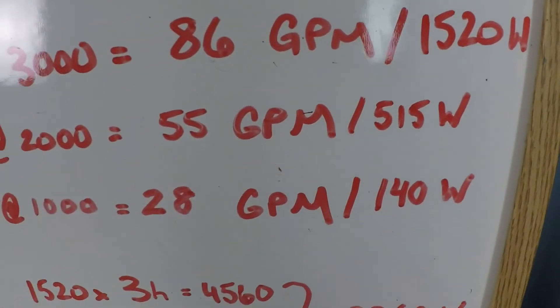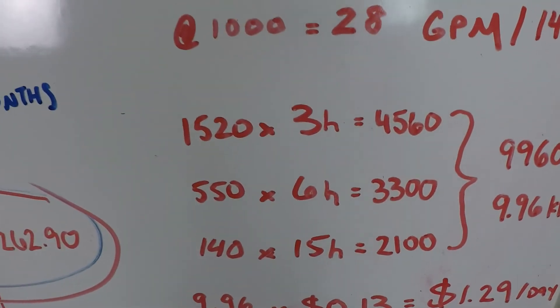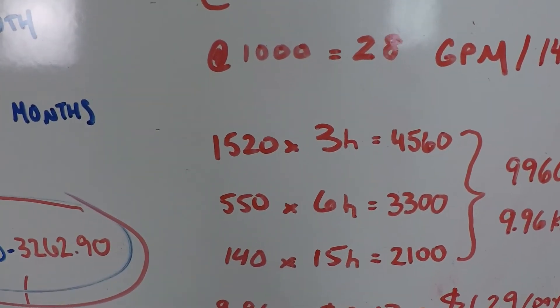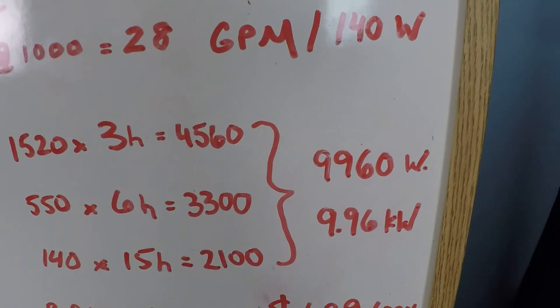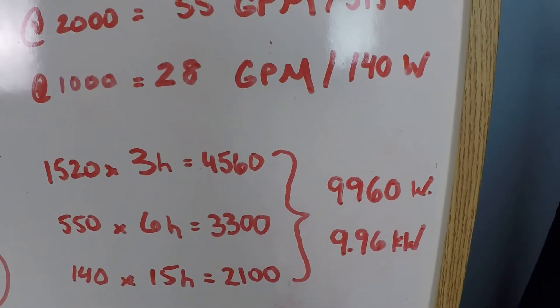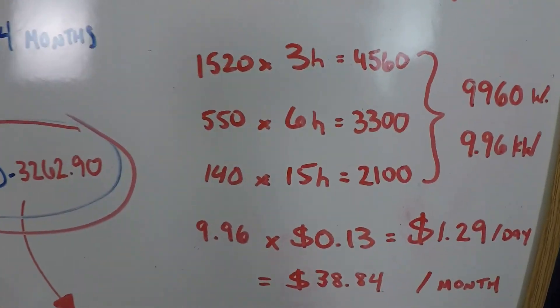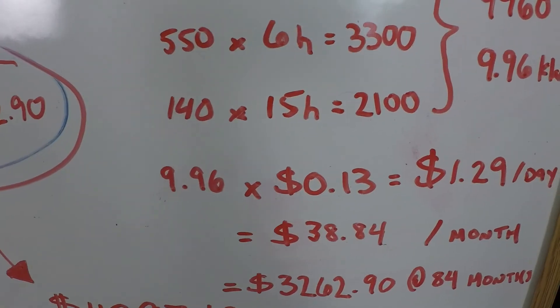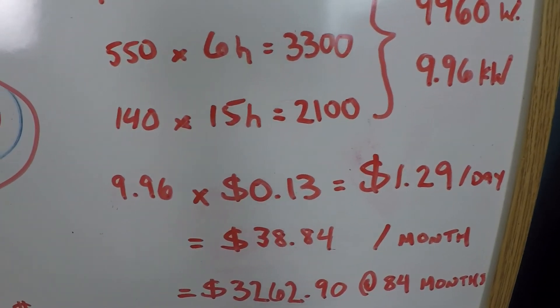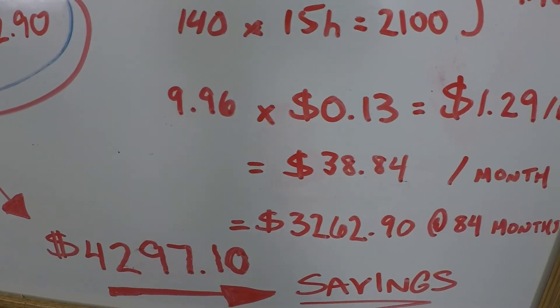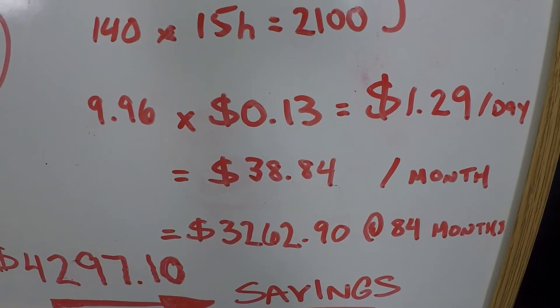So this is even a very conservative estimate at 140 watts, which is good. Because what you're going to see is that the variable speed pump costs substantially less to operate. So when we calculate out our total power consumption over a 24-hour day, we're looking at watts times hours, and we see that the total consumption for a 24-hour day is 9,960 watts, or 9.96 kilowatts. Since you pay for your power by the kilowatt hour, you would multiply 9.96 times the average of 13 cents per kilowatt hour, and that equals $1.29 per day. Extrapolated out, that's $38.84 per month. And on an 84-month service cycle, that total cost would be $3,262.90.